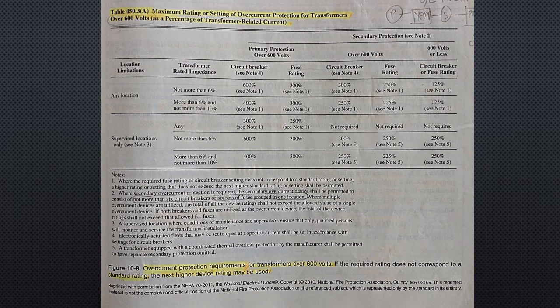Overcurrent protection. Transformers require overcurrent protection; general requirements are specified in section 450.3 of the code. Separate overcurrent protection devices are normally required for both the transformer primary and secondary, with device ratings based on the current rating of each winding. Requirements differ for transformers rated over 600 volts versus 600 volts or less. These requirements are for the transformer only; conductors connected to the transformer must have overcurrent protection per articles 240 and 310.